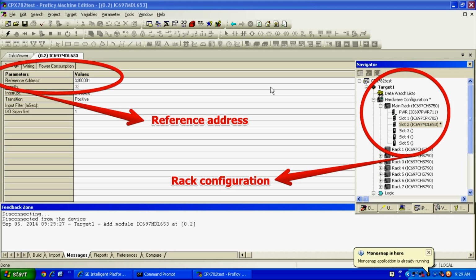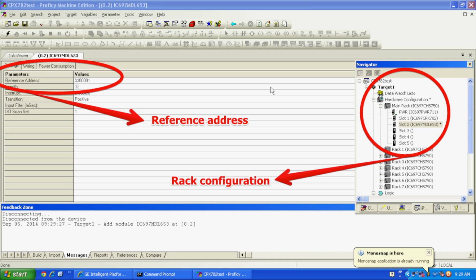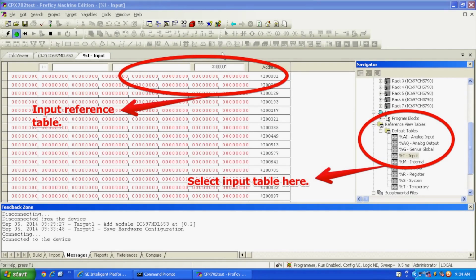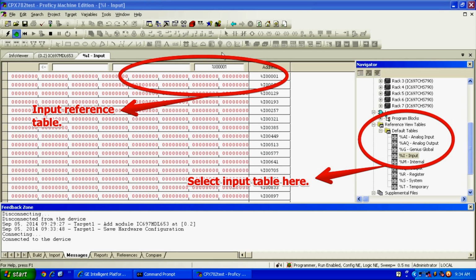Mine for this particular test is %I00001. So when I go to my input table, which is under reference view tables, and expand default tables, the 4th table down is %I, or input. You can double click on that and your input table will show up. It'll be in groups of 8. They should all be zeros, and the goal here, when we probe each terminal, is to make sure those zeros, corresponding to the channel, turn to a 1, meaning we have activity on that channel.